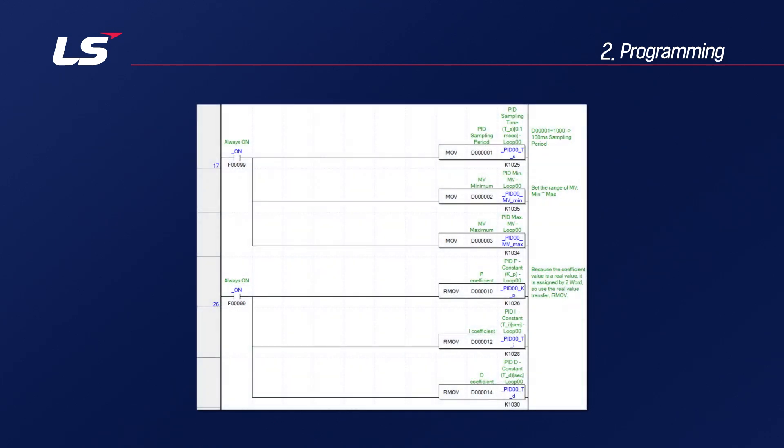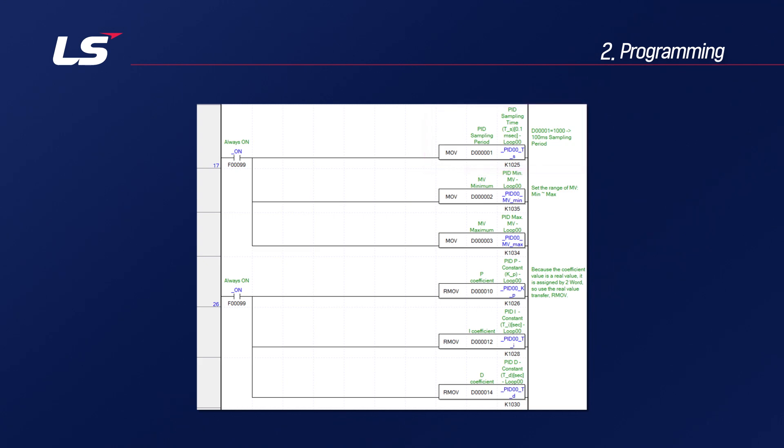The programs you see now are basically the items that go into when you do PID programming. First, put in the control cycle and please set it longer than the PLC scan time. And you can specify the range in which the MV value comes out. You can specify the maximum-minimum value to adjust the output value.